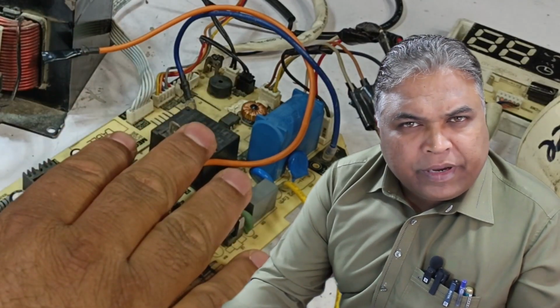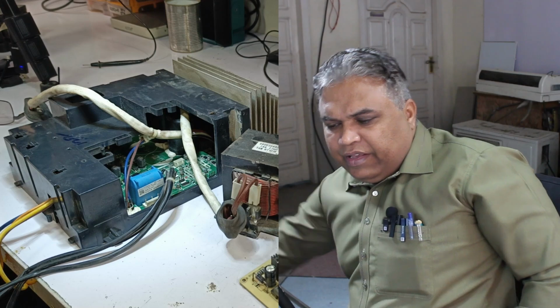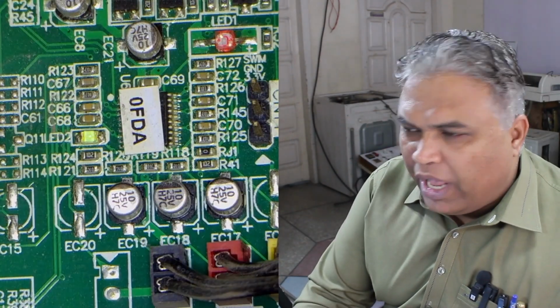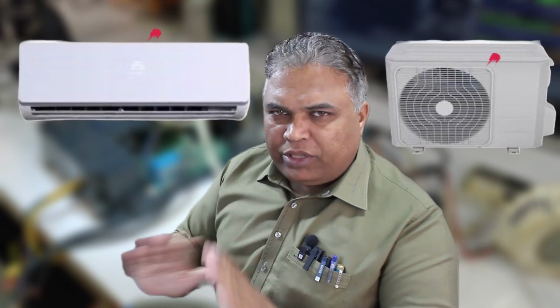Before working further on the indoor PCB, I will first show you how the outdoor PCB is functioning. Now I will turn it on, and as soon as I supply power directly to it, LED 2 turns on, and it has also switched, which means that the PCB is in a working state to some extent. This confirms that the issue lies in the indoor switching relay, which is not functioning, and since the indoor relay is not working, it is not supplying power to the outdoor unit. As a result, the F6 error is inevitable. F6 is a serial communication error where both the indoor and outdoor units shut down and no functions operate. Sometimes the indoor blower motor might still be running, but the system continues to show the F6 error.